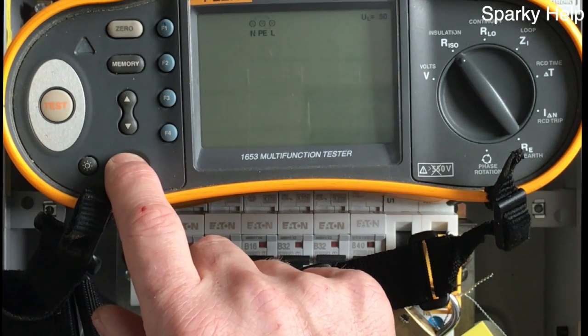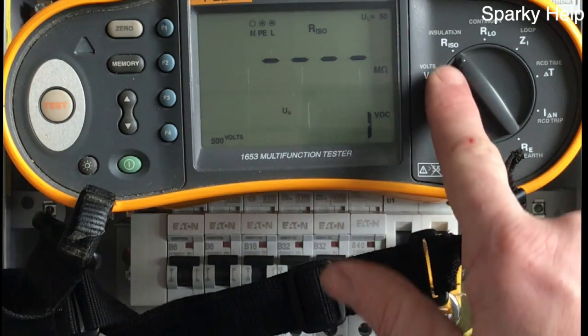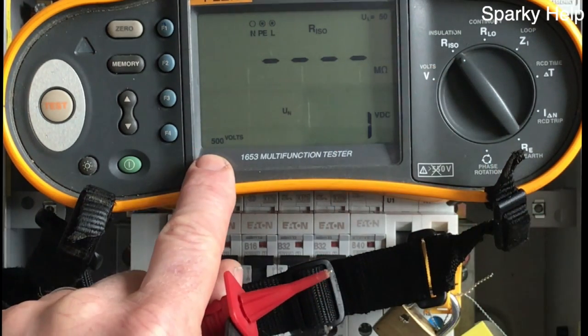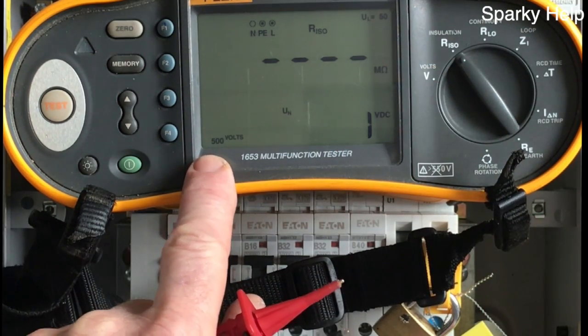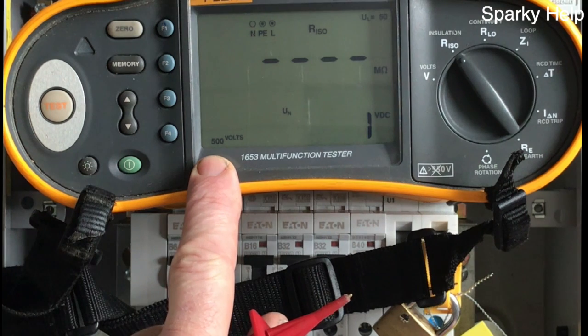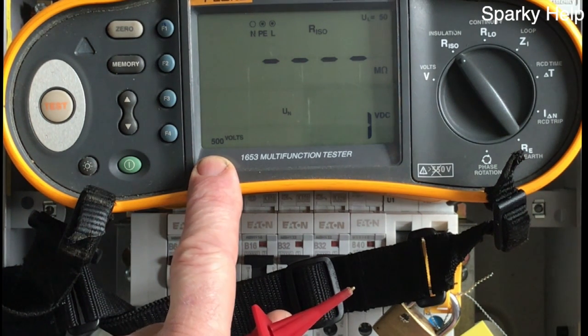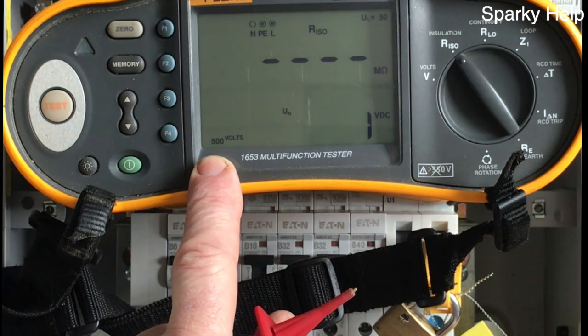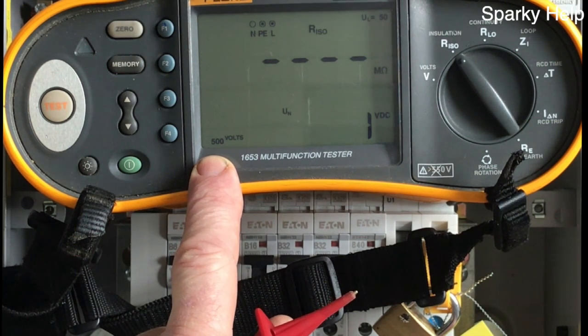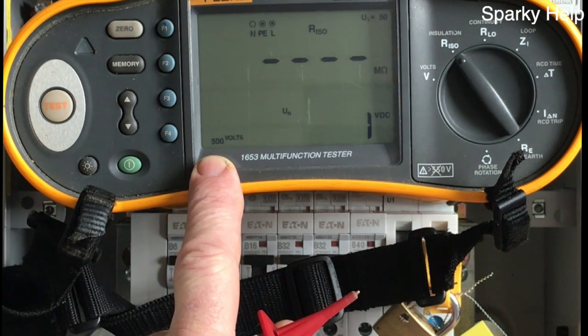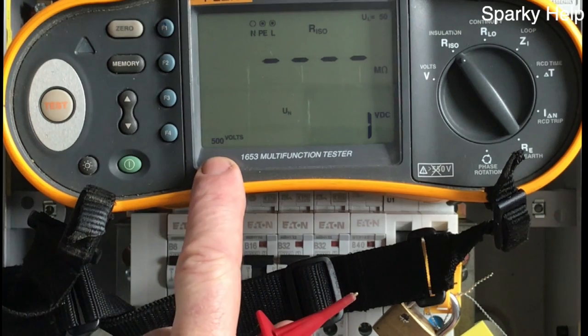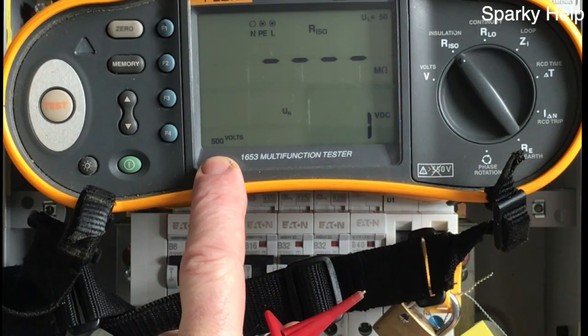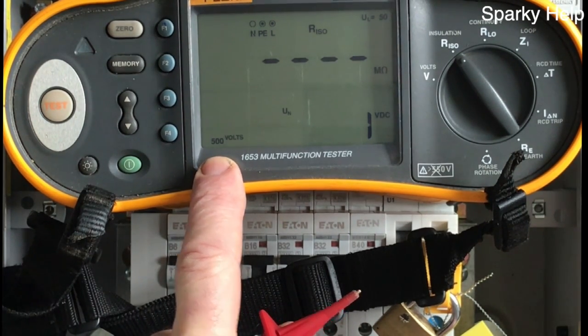So here we have our meter, we turn it on, we go to insulation resistance, and we want to select 500 volts, which is our minimum required for an LV circuit. Remember this is a low voltage circuit, not an extra low voltage circuit, so that's anything above 50 volts AC or 120 volts DC, and we test at 500 volts is what is required.